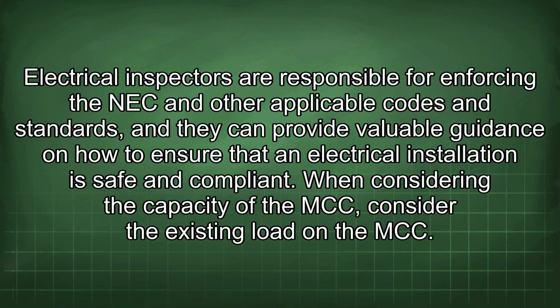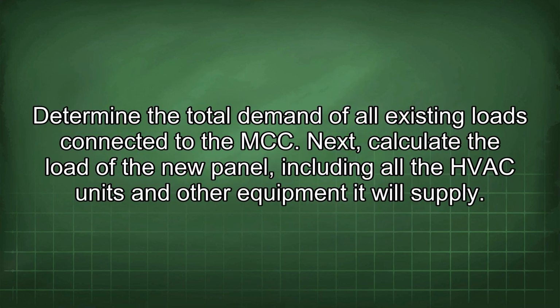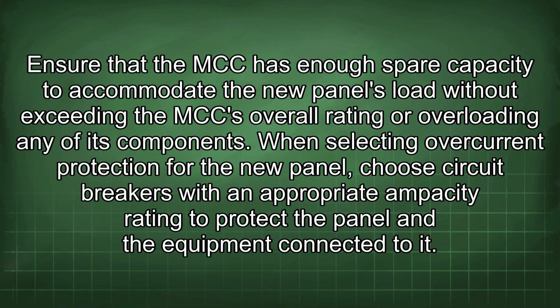When considering the capacity of the MCC, consider the existing load in the MCC. Determine the total demand of all existing loads connected to the MCC. Next, calculate the load of the new panel, including all the HVAC units and other equipment it will supply. Ensure that the MCC has enough spare capacity to accommodate the new panel's load without exceeding the MCC's overall rating or overloading any of its components.